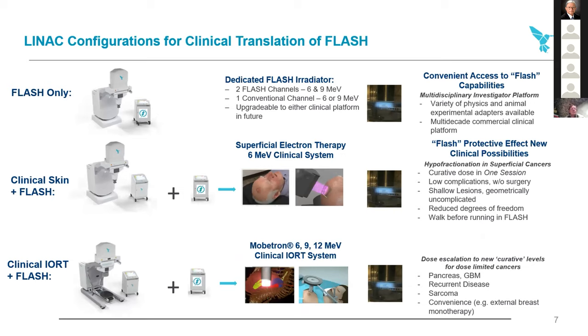We offer it in three different configurations for customers to buy. We sold five of them — we placed five of these this year. You can get it as a flash-only dedicated irradiator, with two flash channels at six and nine MEV at that high dose rate range, plus one conventional channel as a calibration standard. That system would be upgradable to either of the two clinical platforms. You can also choose a system where, if you're not going to keep the flash system busy all the time, you can share its use — get the clinical system, either the derm or the IORT system, and add a flash controller to it. It can be used clinically making money and paying for itself while also doing flash research. This has been a very popular way to approach the market, as our last year has indicated.